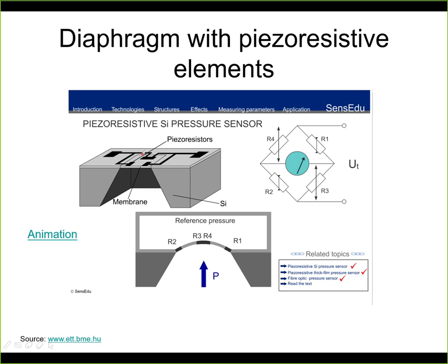Let's take a look at something a little bit different, although the principle is quite similar. And we will slowly move to sensors with electrical output. So we want to connect our sensor to some control system so that we can sense the pressure somewhere and use it for control. Now what you see here on this picture is the principle of basically all pressure gauges that you can find today, and they have the electrical output. Here we can see a diaphragm, and in this picture it is shown like a diaphragm on a chip, but it can also be a diaphragm made from stainless steel, brass, or copper, and then you can have normal force sensors, so strain gauges mounted on the diaphragm.